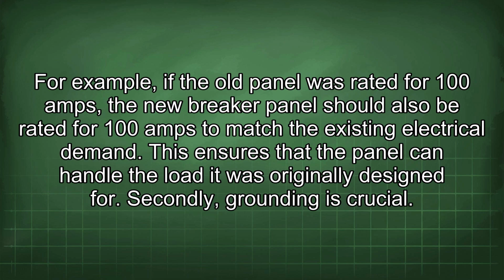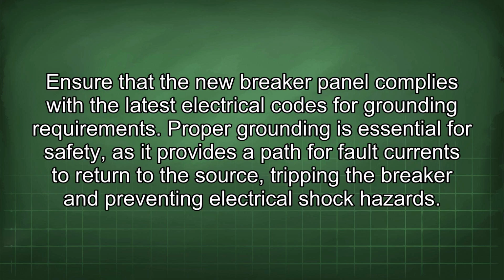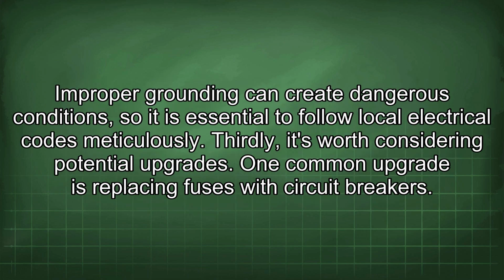Secondly, grounding is crucial. Ensure that the new breaker panel complies with the latest electrical codes for grounding requirements. Proper grounding is essential for safety, as it provides a path for fault currents to return to the source, tripping the breaker and preventing electrical shock hazards. Improper grounding can create dangerous conditions, so it is essential to follow local electrical codes meticulously.